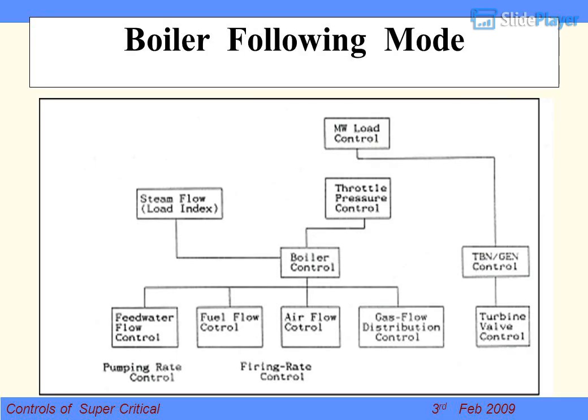Boiler-Turbine Control. Let us see how any power plant controls the load or generates MW. There are two components: boiler and turbine. The turbine has its own controls; since it consists of a rotating mass of around 200-tonne rotor, many precautions are taken so that at no point should it go into an unsafe zone. The ultimate aim of the boiler is to generate steam at required pressure and temperature for the turbine. Everything is so dynamic in the boiler that very complex boiler control is required. We burn fuel, and need air and water, so all the controls are required. Since we are burning fossil fuel, the boiler manufacturer ensures the boiler remains safe in all operating conditions. Turbine follows certain standards while the boiler follows a mode.